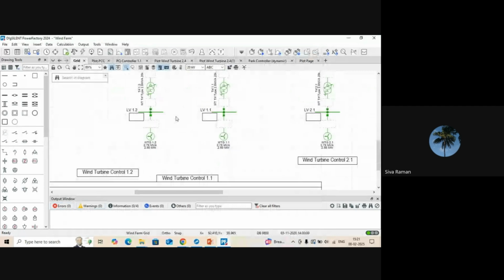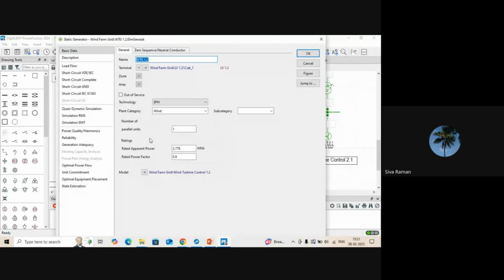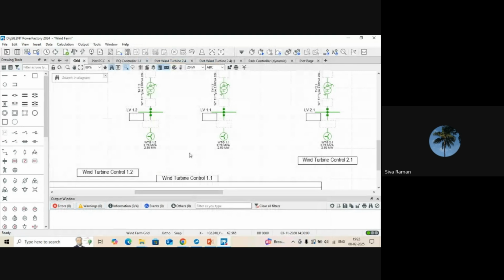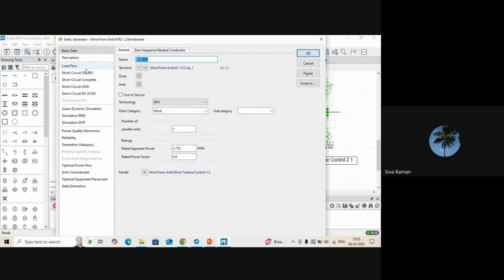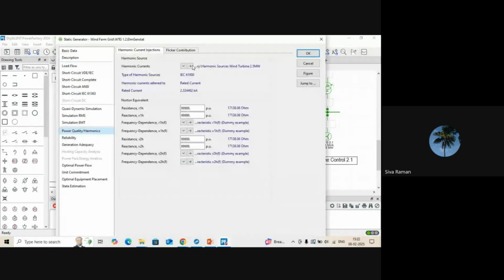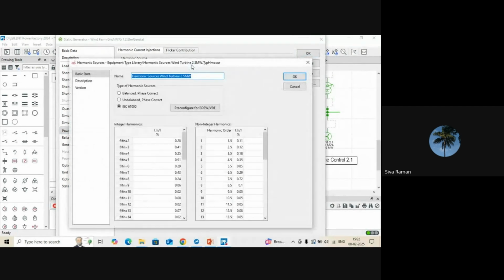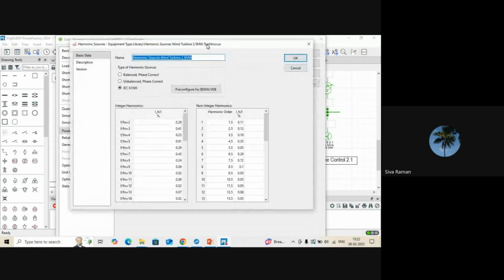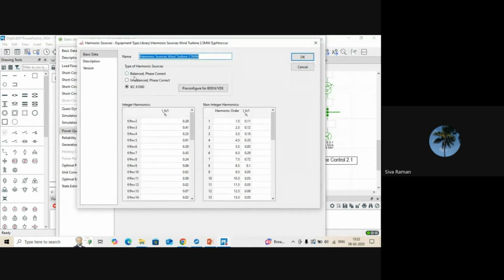So here, modeling of harmonic source. The wind turbine generator is the major source of harmonics, so we have to model it. On the power quality page, we have to model harmonics. In harmonics, we can model in multiple ways. One is the balanced method, another one is the unbalanced method, and the third one is the IEC method. IEC 61000 is a standard, so these values are modeled as per the standard.